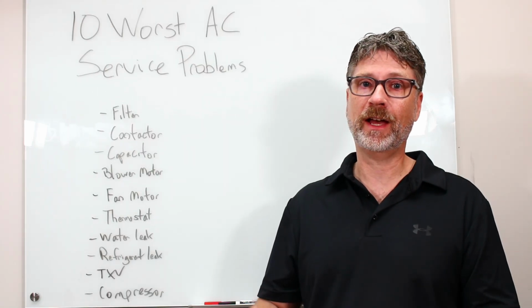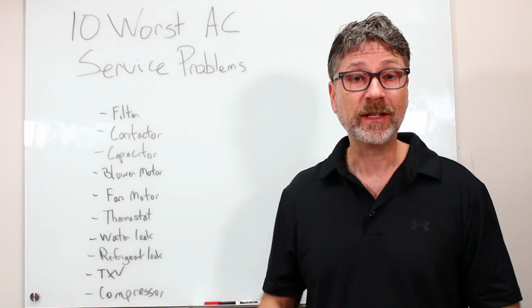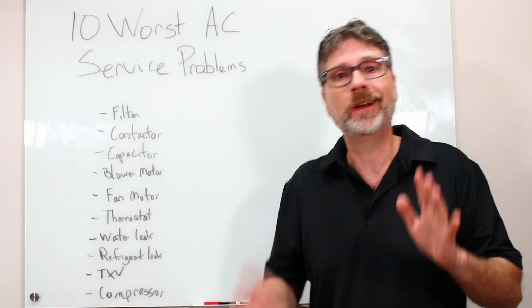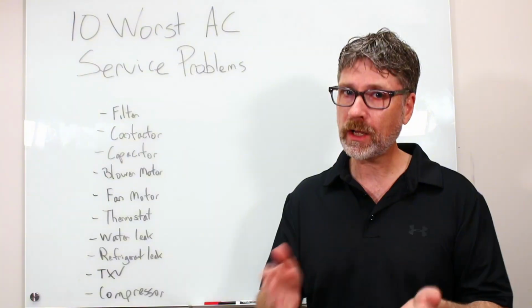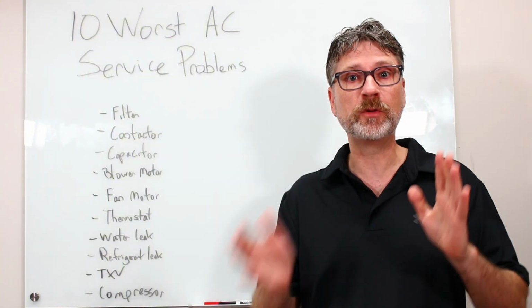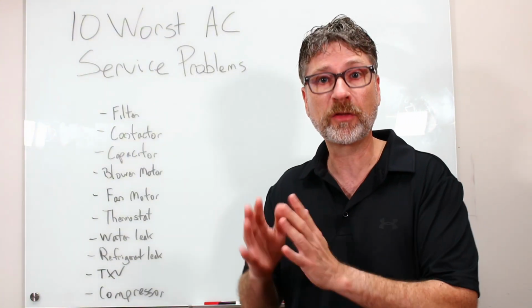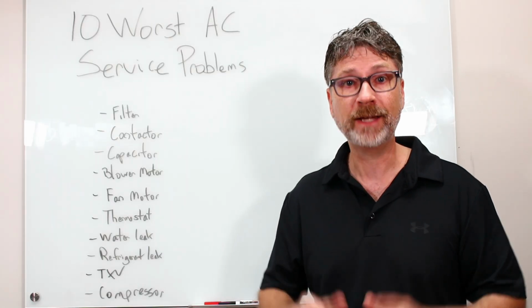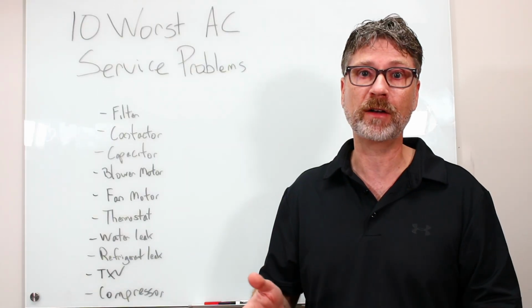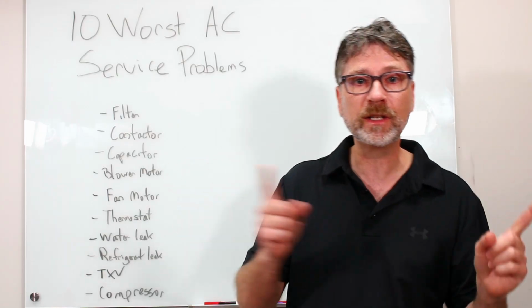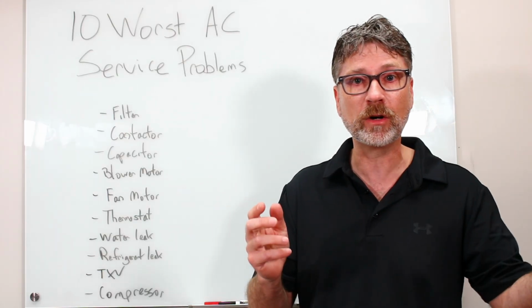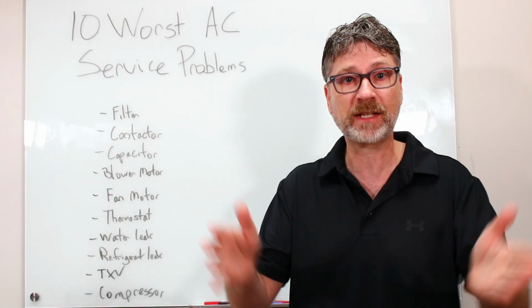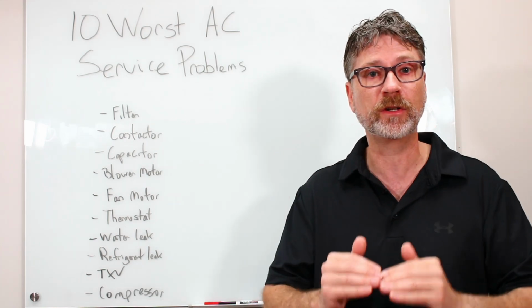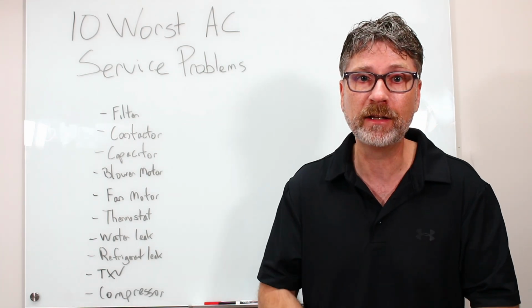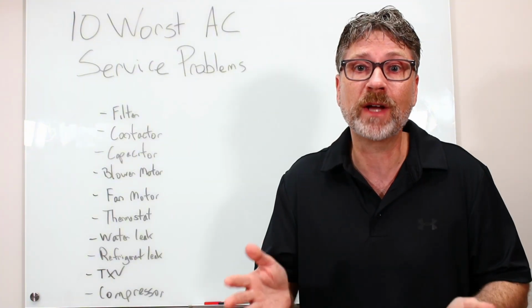Number 5. The thermostat in your system is the brains. In simple models, it just tells the unit on or off. But in more complicated models, it's choosing between first and second or maybe even third stages for heat and cool. And in communicating, in other words, high-end models, the thermostat is constantly coordinating efforts between the indoor unit and the outdoor unit to maximize efficiency and the reduction of humidity. As a complicated electronic device, these too sometimes fail.